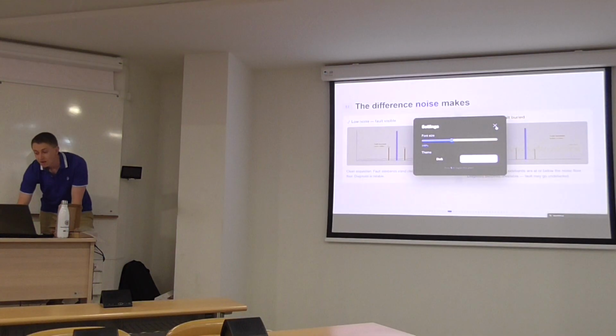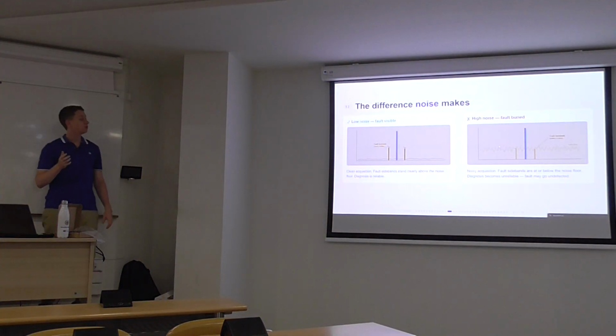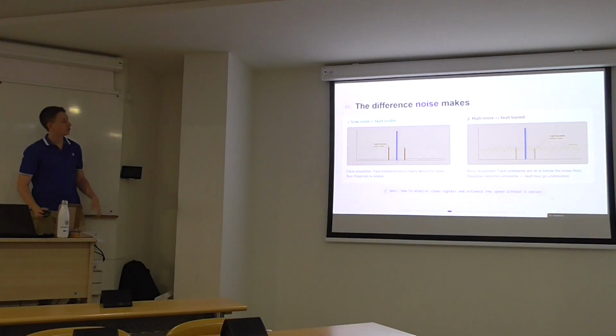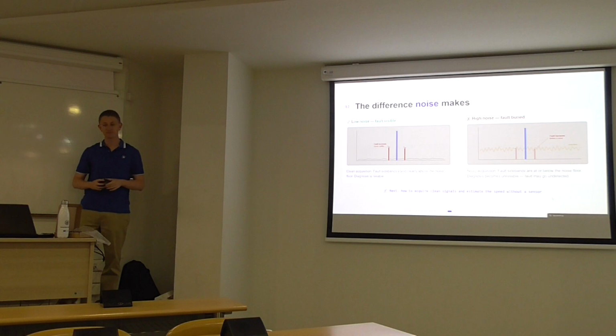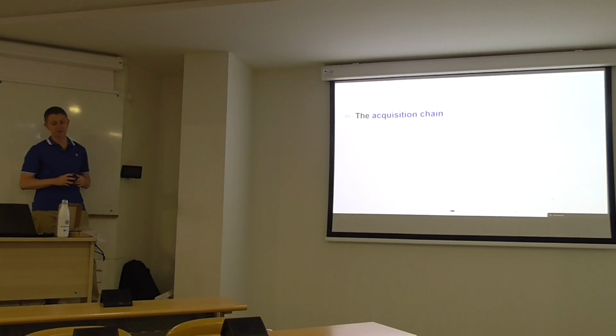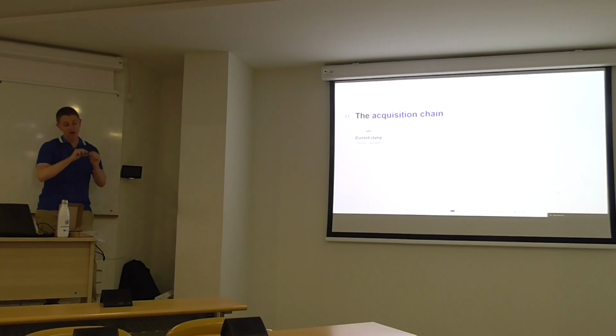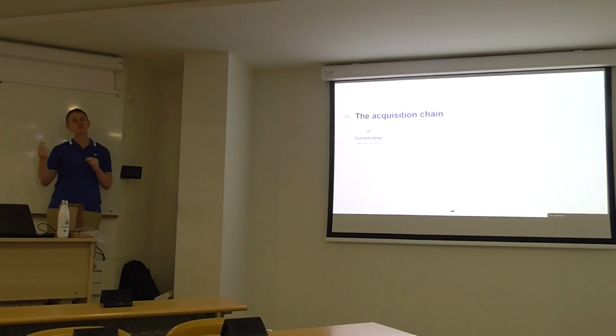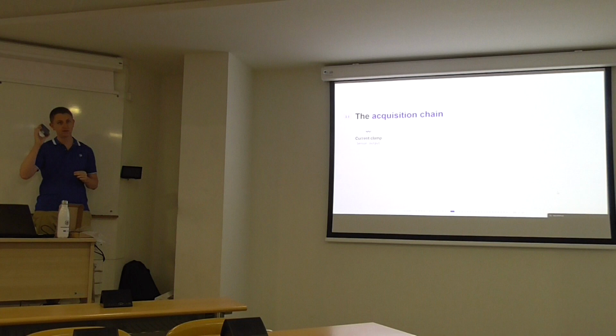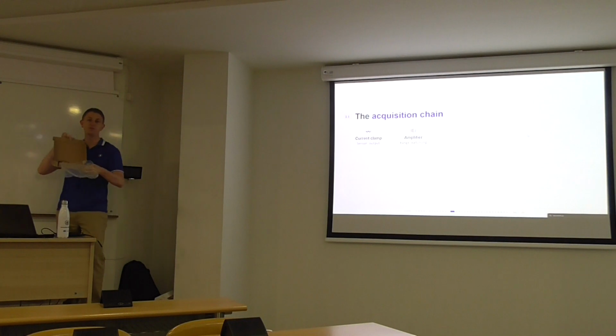So it's super important to acquire a signal with the lowest noise possible. So next, I will show you how to acquire these clean signals. First of all, the acquisition chain. Once again, we have the current clamp. With the clamp, we measure current, but the output is voltage. So we need that output voltage to match the input range of our ADC. And for that, what we need is an amplification stage. It, for example, is part of that electronic circuit that amplifies the signal.